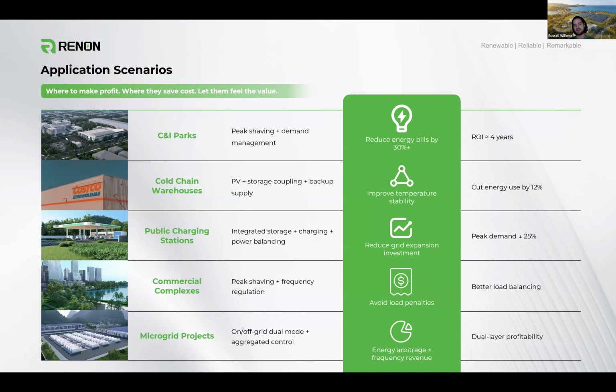As a result, it really brings down your peak demand charges. You're also able to do that intentionally by discharging when you have high demand charges. Maybe you're running a testing facility where your test is very energy intensive—for 3 hours once a week you do a massive power discharge for scientific testing. In those circumstances, having a megawatt of storage and an extra 500 kilowatts of power can significantly reduce those demand charges for those brief, sharp periods.